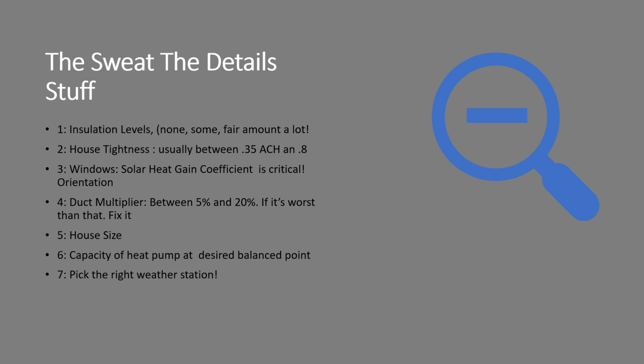Duct multiplier, typically between 5 and 20%. If it's worse than that, you really should fix it. It's hard to make people comfortable with heat pumps with leaky, uninsulated ducts. And insulation is just as important on that ductwork as making sure the air doesn't leak out of it. House size is often important, but as we said, R values and U values and ACH and duct leakage probably have a bigger role, but obviously the larger house, all the other things being equal, will require a larger system. Capacity of the heat pump, the desired balance point, we're using a 30-degree balance point. And again, you have to look at the detailed capacity tables provided by the manufacturer. And oh yeah, number 7, make sure you pick the right weather station.